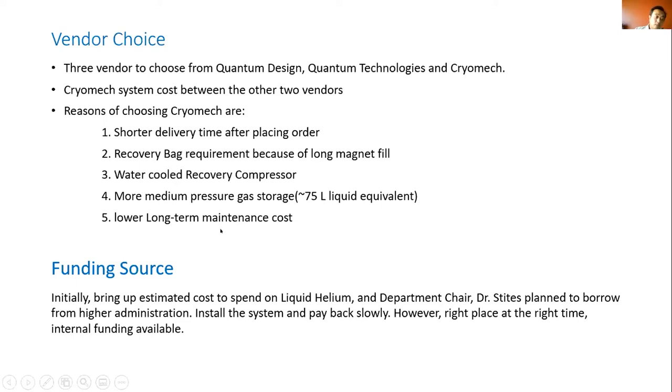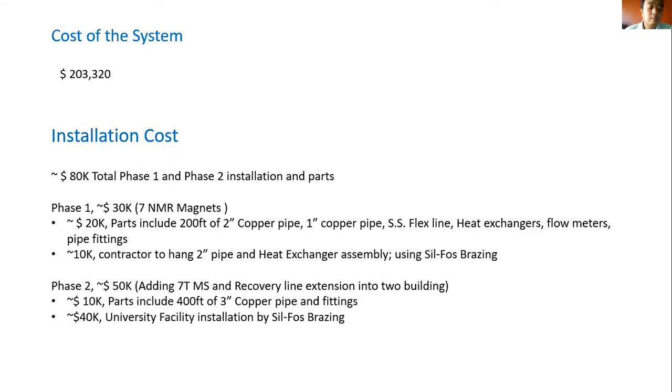Another important thing is long-term maintenance costs. It seems Cryomech has the lowest. The funding source is internal. The cost of the system is a little over $200,000. Installation cost, we have a total of $80,000 for two phases. The first phase is recovering boil-off and magnet fill from seven magnets from two labs, and that cost about $30,000.